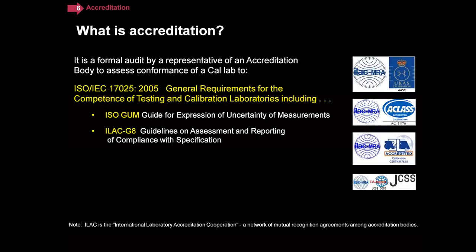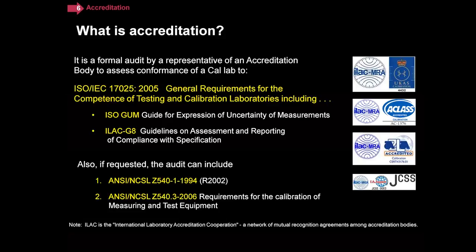We talked about most of these in module five. The standard that is always included in an accreditation is ISO 17025, and you can see just from the title why that would be the case — it's the competence of testing and calibration laboratories. Part of 17025 covers how you use the ISO GUM for measurement uncertainty and whether you're observing the guidelines on assessment reporting via G8. If a lab chooses to, they can also be accredited to Z540-1 or the newer replacement Z540.3.